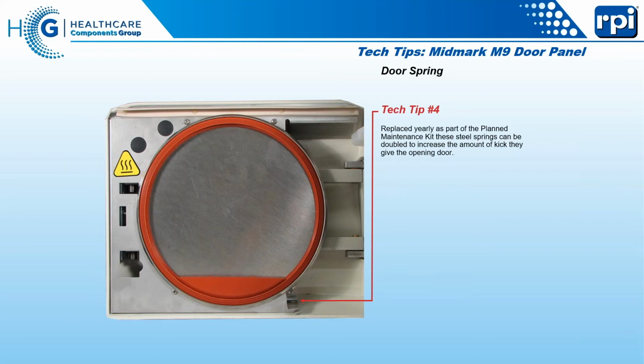There's a spring that's used to pop open the door, and if you find it is weak or not getting the door where you want it to be, it can be doubled up. We put 2 of them in the planned maintenance kit. This picture points it down, but it can also be turned 90 degrees sideways to get even more force out of it. These are part of the planned maintenance, and that's why we give you 2, just in case you don't like it.